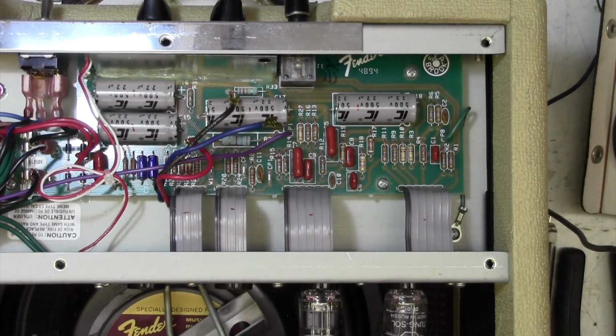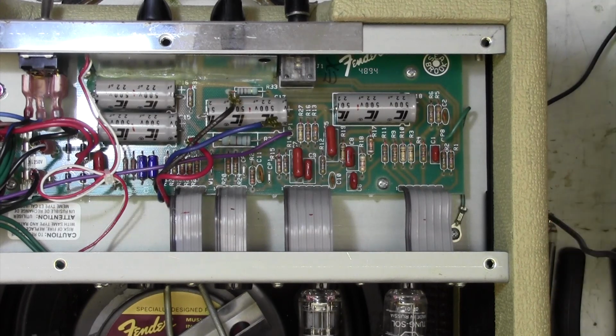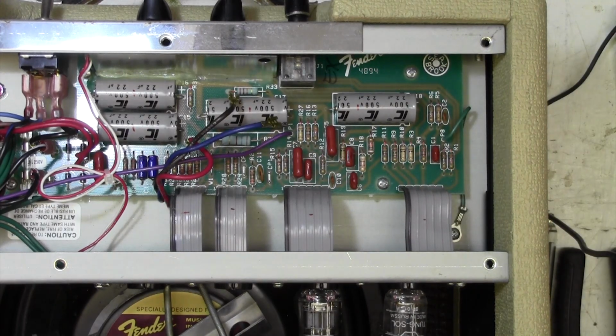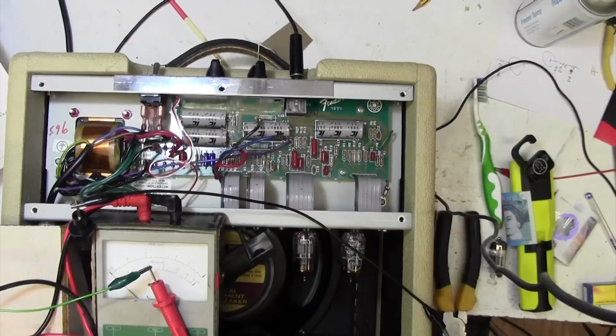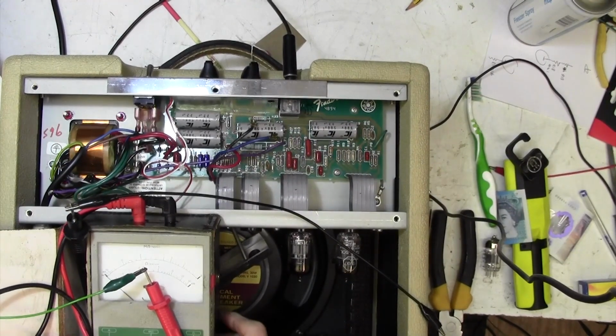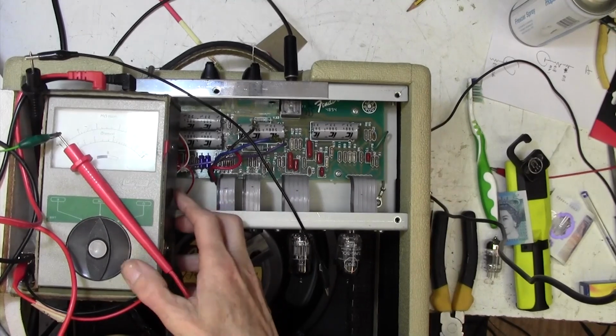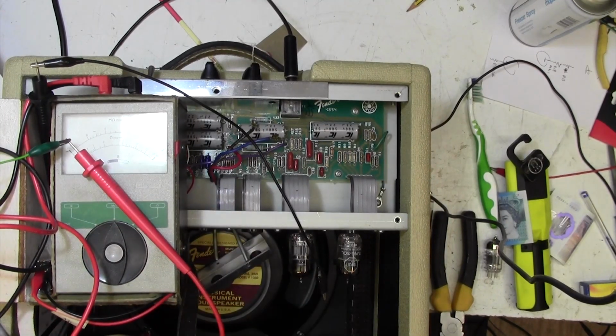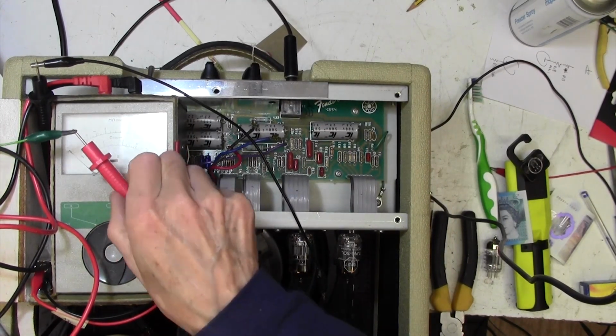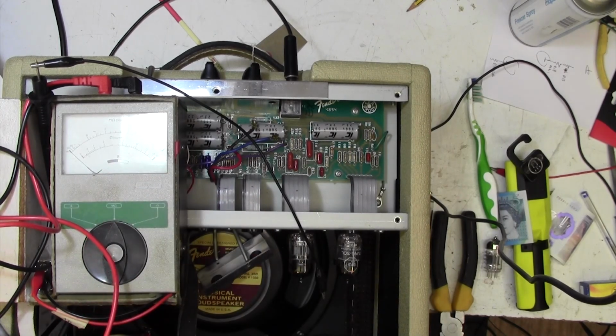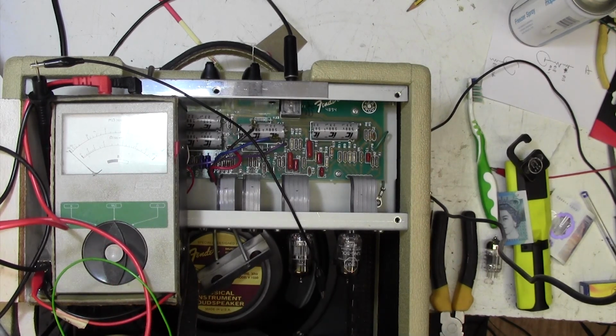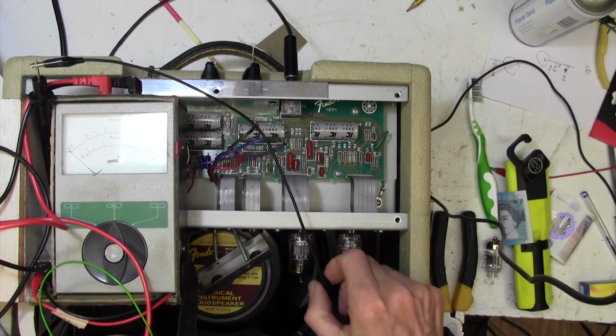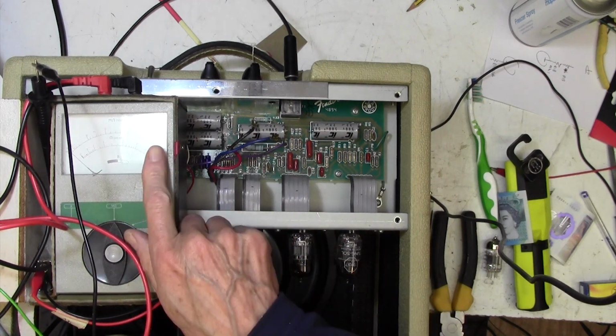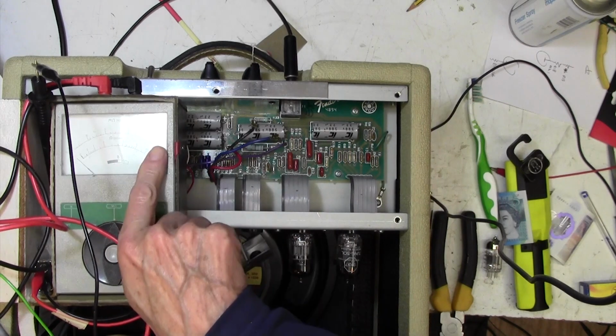Let me show you what I was going to do, I think you'll find this interesting. Right, I've got what's called a Megger here. You may or may not be familiar with it. It's for testing insulation, to make sure something's really insulated. It's all very well putting a meter across something and reading an open circuit and saying the insulation's fine, but you want to know if it'll break down under high voltage. This Megger puts out 500 volts and measures the resistance.